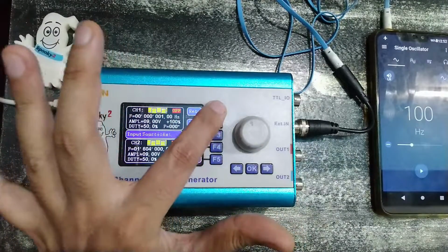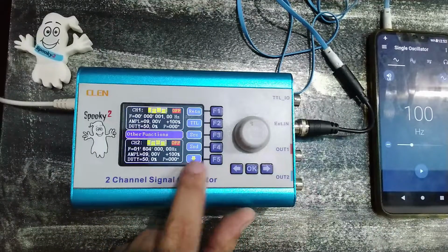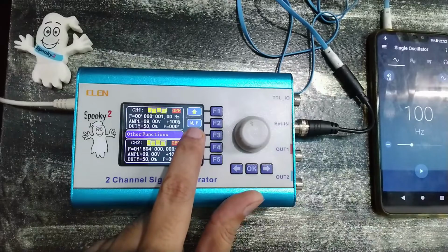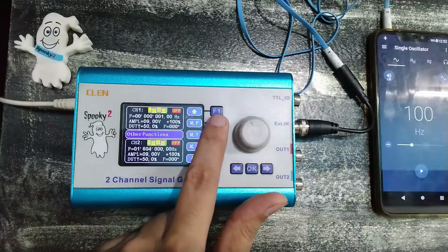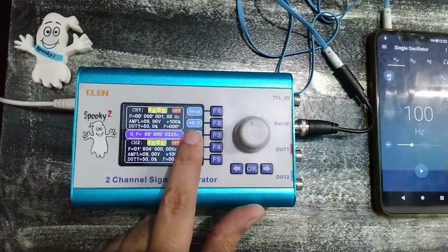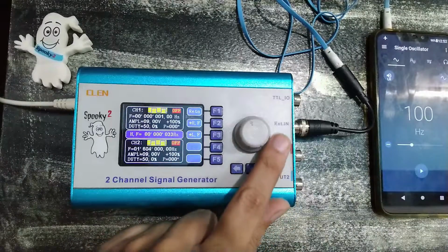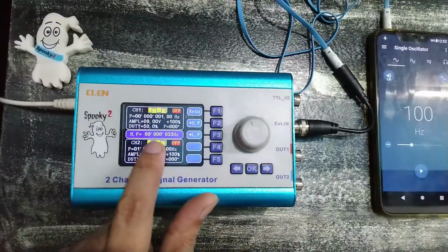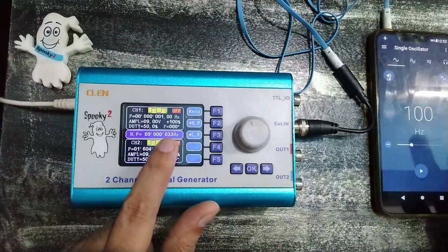What you have to do is press the return button, and in the very next menu, go down, press the F5 button and press MF, that is measure frequency. So I have to select this. Please remember a very important point, that when we press this button, there are two ranges now, which are high frequency mode and low frequency mode. So when we do external input, when we select this option, remember that the frequencies displayed on the screen will increment by the factor you have shown here.